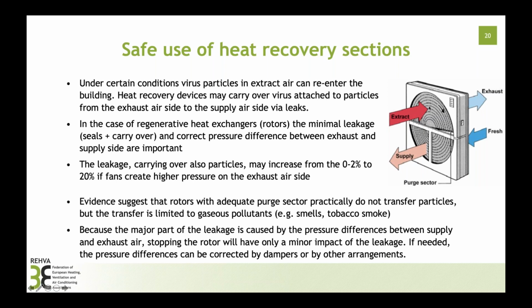So all types of pollutants, gas phase pollutants and particulate matter, will follow with air leakages in ventilation equipment. And this has been suspected especially for these rotary heat exchangers, where you have this moving mass in between extract and supply air flows. There is evidence that these devices do transfer gas phase pollutants. Tobacco smoke is a good example of a gas phase transfer, and it applies also to other types of odors. This is well known, but there is also available evidence that these devices do not transfer particulate matter. And this virus will classify as a solid particle because it is in these desiccated expelled droplets, so there is no direct risk for virus transfer via these rotors, but the risk will apply if there are air leakages.